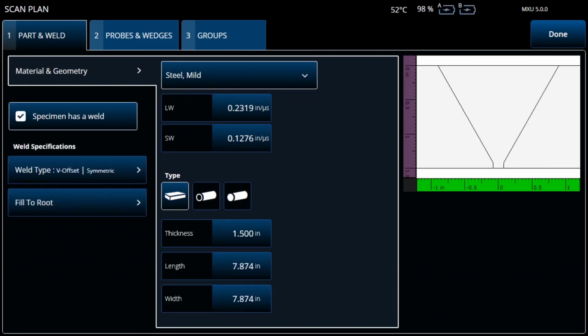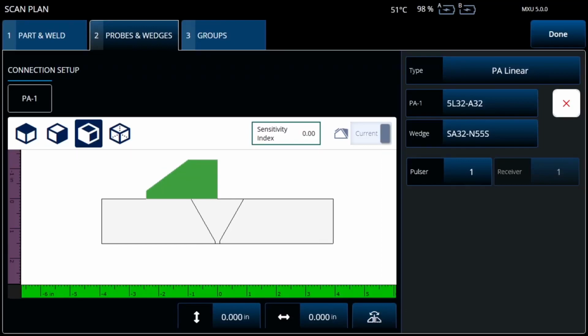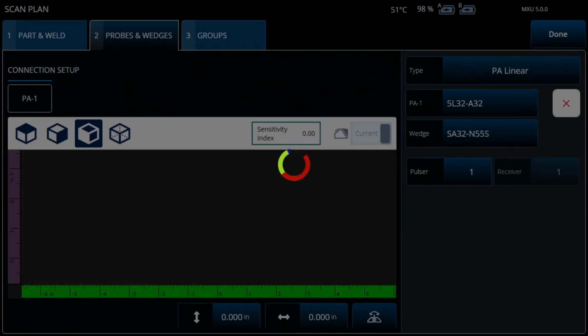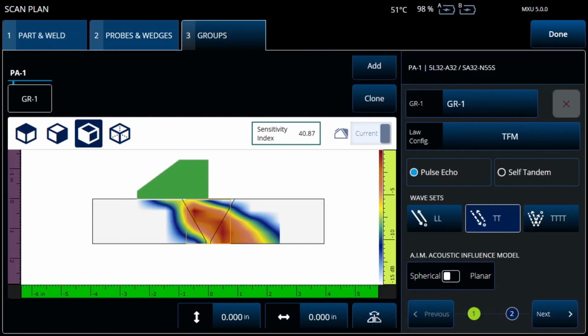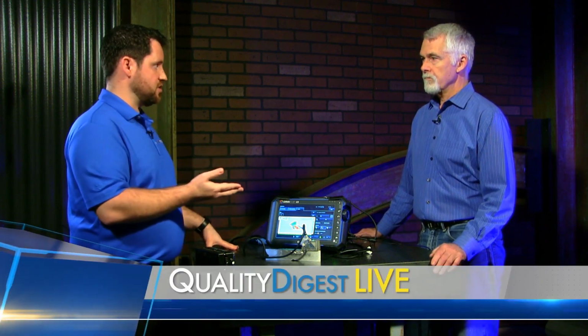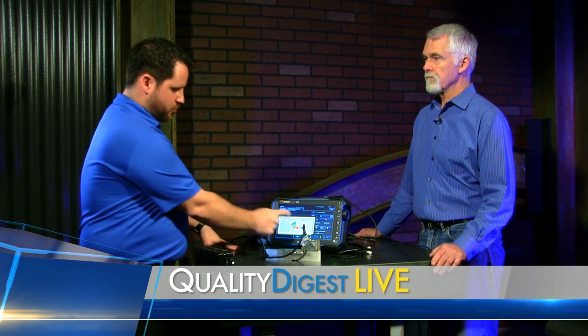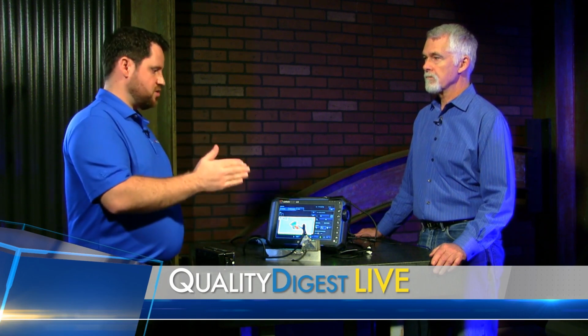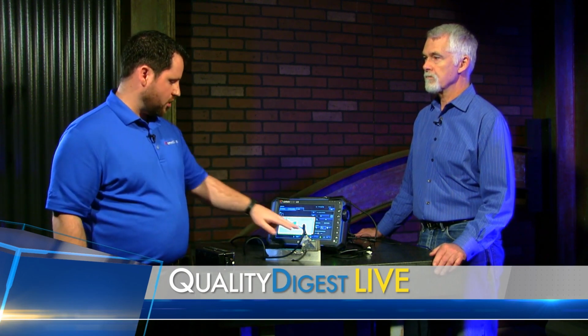So the same way we adjust the part and the material type, the thickness, the picture of the component, the probes and the equipment, all that works exactly the same. But then when you get down to the setup part of the TFM, it is a little bit easier in that you're just adjusting where the image takes place. It's just a square that you're adjusting, or what we call the zone on here. Okay. There's a couple tools that we've added to the X3 when it comes to that type of inspection to make it easier on the technician to know where the probe should be sitting, where that image should be coming from, and what we call our AIM tool.